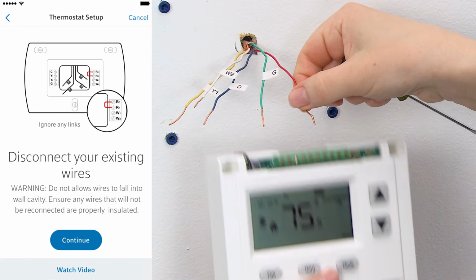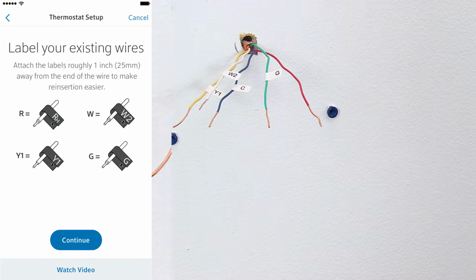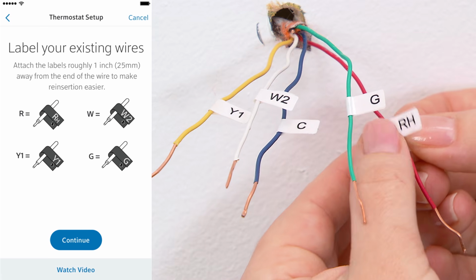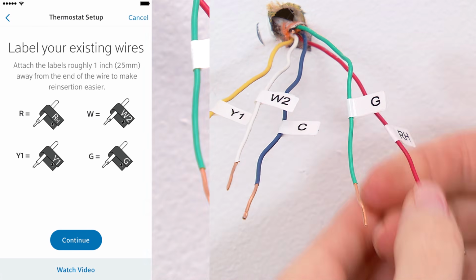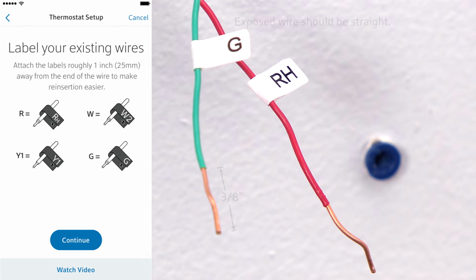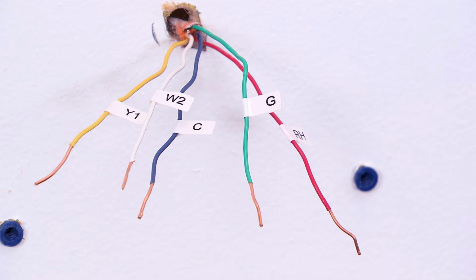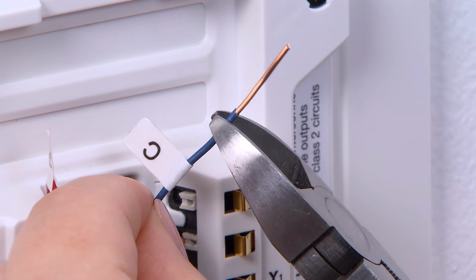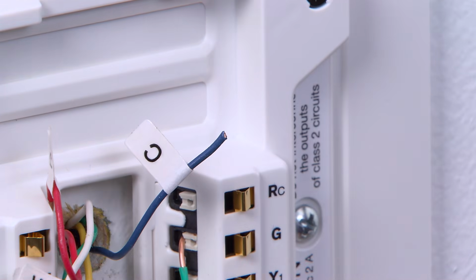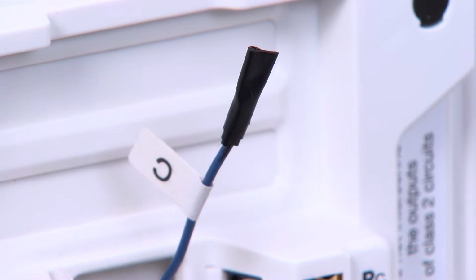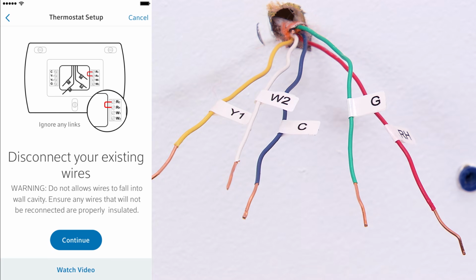Now, disconnect each wire one at a time and label it with a wire label. Do not place the labels too close to the ends of the wires, as this will make insertion difficult. Make sure 3/8 inch of the wire is exposed. Your new wire configuration may not require you to connect all your old wires. If that's the case, make sure any wires that are not reconnected are properly insulated. To insulate unused wires, trim the exposed wire and then wrap the end in electrical tape. Be careful to not allow any wires to fall into the wall cavity.